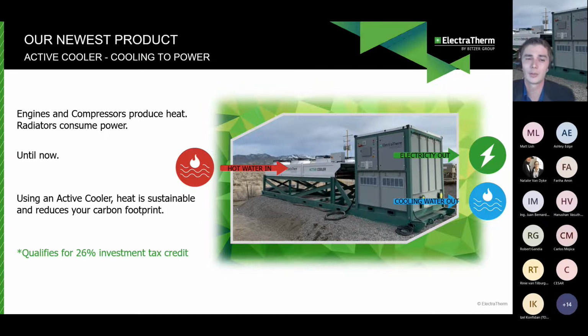Installing these units is very similar to a radiator installation. So it's a hot water supply and return, and then a motor rated circuit breaker for your electrical connection, because we utilize an induction generator. So it's very similar to installing a motor of equivalent size. If you were installing a pump that was roughly 150 kilowatts load, that would be the type of breaker you would need for a 6500.